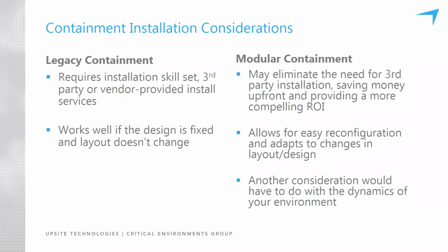Thanks, Lars. So I'm going to just dovetail on some of the things Lars just said, and we'll talk about considerations around installation for both mechanically attached or legacy containment as well as for modular. So legacy containment solutions oftentimes require skilled installation crews that may need to travel to the job site. Depending on the type and duration of the install, this could add up to a significant component of the overall project cost, but it's also sometimes unavoidable and absolutely necessary. With modular solutions, like you just heard from Lars, and like those offered by Upsite, they utilize magnetic attachments, these can eliminate the need for a third-party installation, assuming you have the available staff, the skill level, and the time to do that self-install. If ROI is a necessary component for selecting a containment solution and your site conditions allow for the use of modular containment, then selecting a modular solution can offer a considerable cost savings and a much quicker ROI.